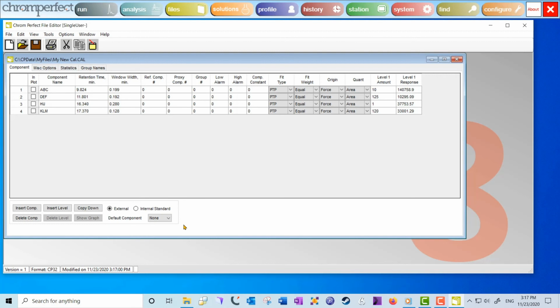The solution is to apply to the unidentified peaks the calibration curve for one or another component in the calibration file. This component is called the default component for the unidentified peak. New calibration files have no default component, so the amounts of the unidentified peaks are all 0. You can change this setting to specify a specific component, or you may specify the previous, the next, or the nearest component.